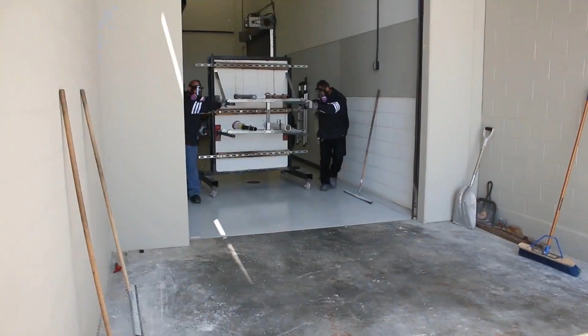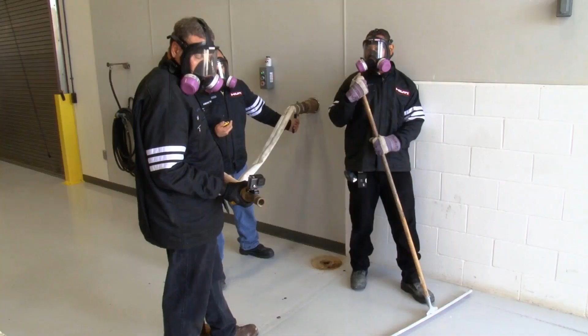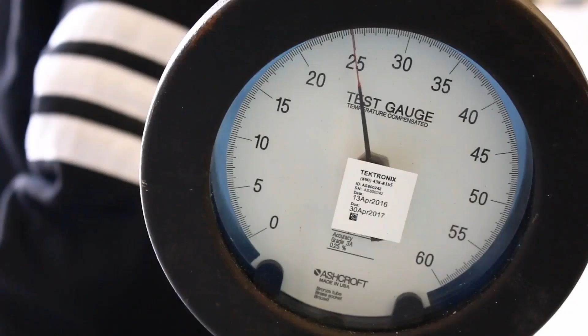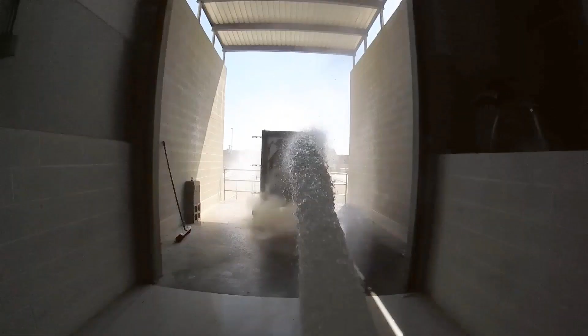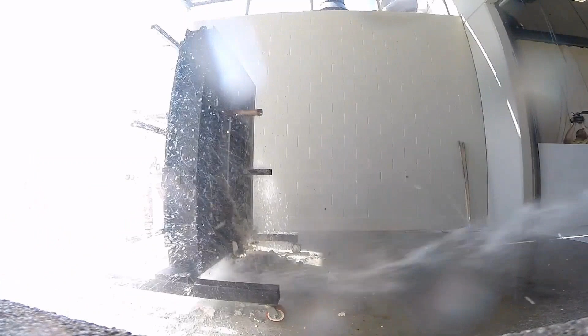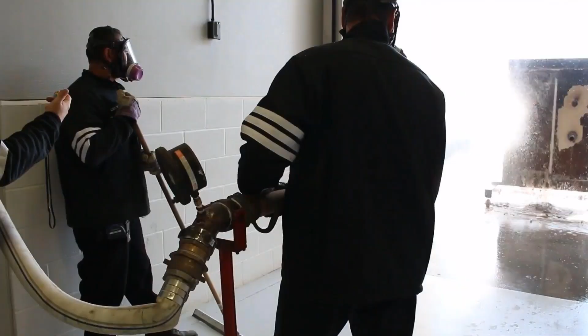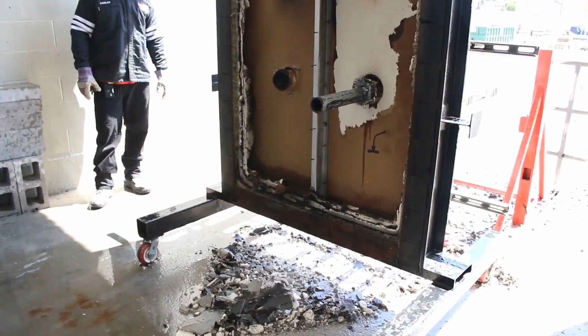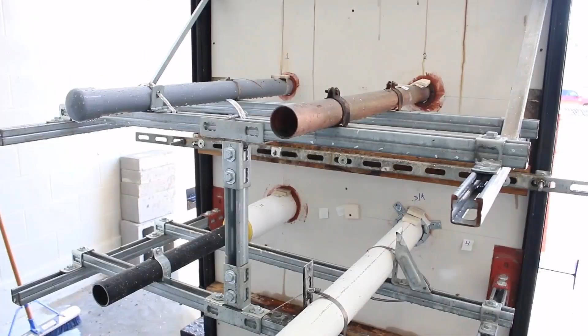The fire side of the assembly will now be subjected to a powerful stream of water. We use an authentic fire service hose and nozzle during the test. Distance from the wall, water pressure, and spray duration are all dictated by ASTM and UL test standards. As the water hits the superheated sheetrock, it practically explodes from thermal shock and impact of the water. This type of test helps determine structural integrity of the fire stop system. As the charred wall disintegrates, most of the assemblies and leftover pipe go with it. But on the non-fire side, the assemblies remain in place exactly as designed.